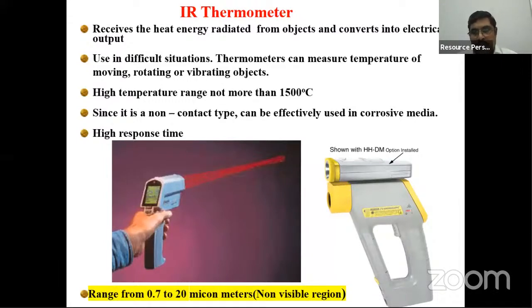Again, these are very, very rapid, and when you focus on your body, you can get the reading. Here, one important thing is the focusing distance. For medical application, the focusing distance should be about 1 meter to 1.5 meter. The focusing distance is the distance between the target and the instrument, and it varies with the focal area. Basically, it is the focal area divided by the distance.